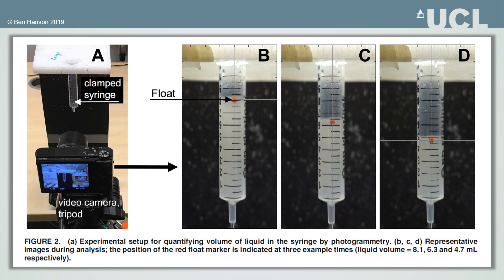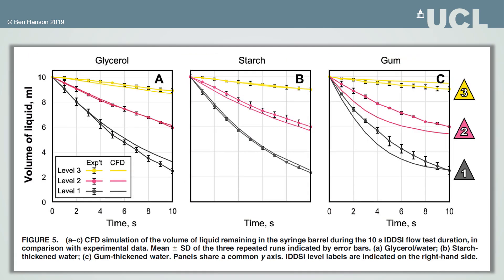Experimentally we wanted to measure how the liquid was draining during the flow test, as well as getting a reliable measure of the final liquid level at 10 seconds. So we created a rig which used video and motion tracking software to plot the liquid level versus time. Here are some results comparing the simulated and measured liquid level over the 10 seconds of the flow test. Because the flow is gravity driven, the level falls fastest when the syringe is full at the start and then slows as the liquid level drops.